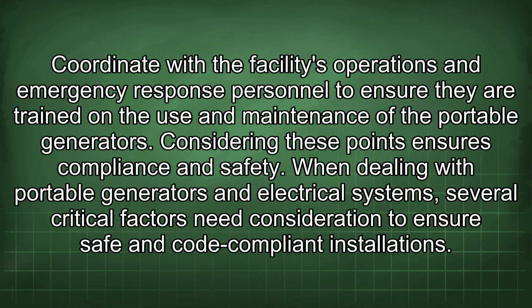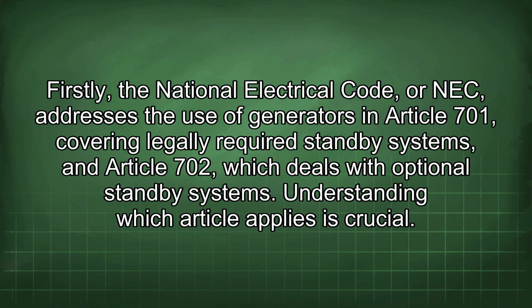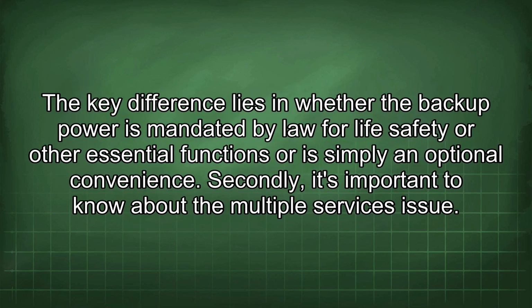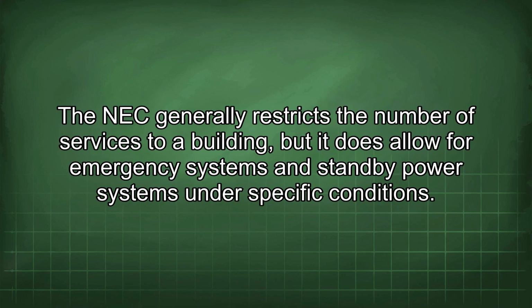When dealing with portable generators and electrical systems, several critical factors need consideration to ensure safe and code-compliant installations. Firstly, the National Electrical Code, or NEC, addresses the use of generators in Article 701, covering legally required standby systems, and Article 702, which deals with optional standby systems. Understanding which article applies is crucial. The key difference lies in whether the backup power is mandated by law for life safety or other essential functions or is simply an optional convenience. Secondly, it's important to know about the multiple services issue. The NEC generally restricts the number of services to a building, but it does allow for emergency systems and standby power systems under specific conditions.